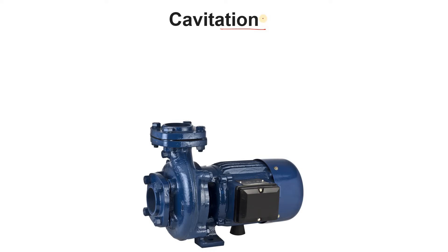We have already discussed cavitation in our previous videos — the science behind it, prevention, and there are four or five videos about cavitation you can watch. In short, cavitation occurs in a centrifugal pump where the pressure at the impeller is minimum. If the pressure of the liquid at that temperature goes below the vapor pressure of that liquid at that temperature, boiling will occur.